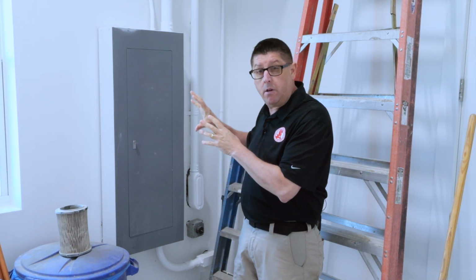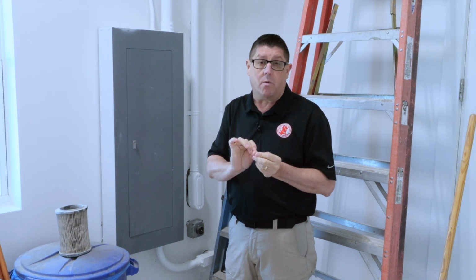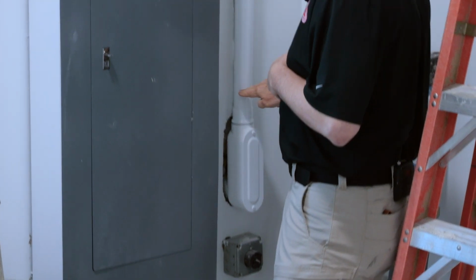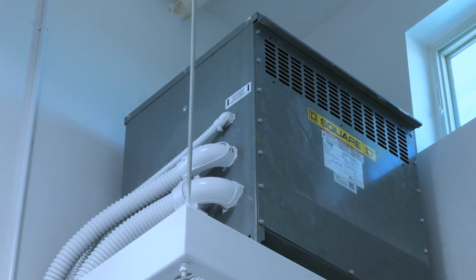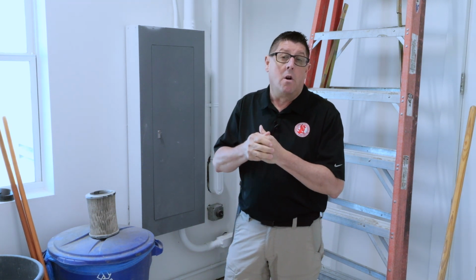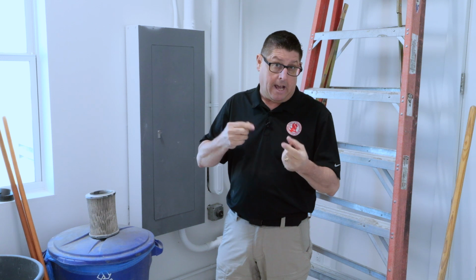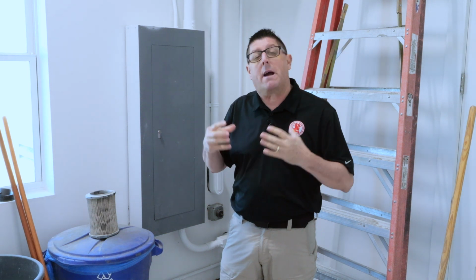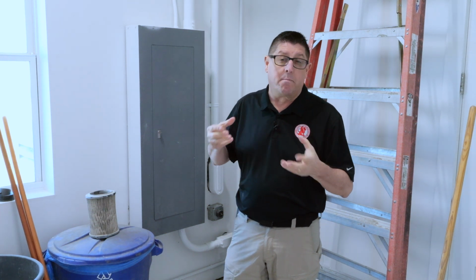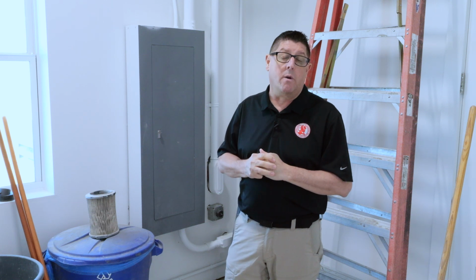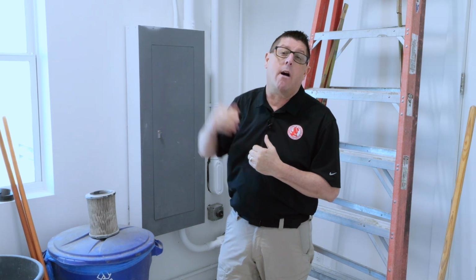So how do I know this is the transformer that's servicing this panel? I can follow the conduit. Where our conduit comes into the building here, travels up the wall, into the transformer, out of the transformer, into the panel. And by following the conduit, I can actually follow the conductors that are inside the conduit and can connect the dots, going, this transformer services this panel. You could also sometimes find it by labeling, but in our case, I can simply witness and view our conduit with the conductors inside going in and out of the transformer.